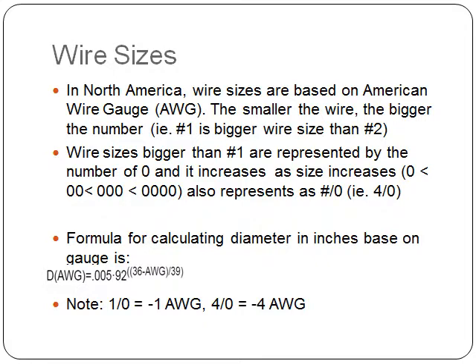For example, four-slash-zero equals four-aught. The formula for calculating the diameter in inches based on the gauge is: diameter in inches equals 0.005 times 92 to the power of (36 minus the gauge) over 39. For aught sizes, you replace the gauge with a negative number — so for a one-aught cable, AWG is replaced by negative one, and for four-aught, it is replaced by negative four, and so on.